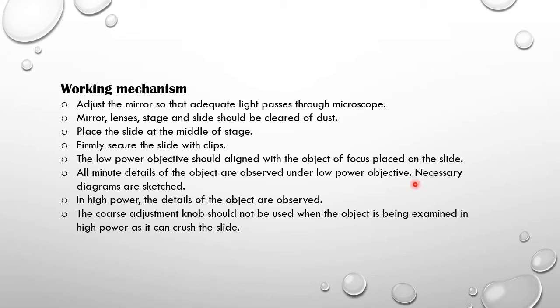Under low power objective, necessary diagrams are sketched. In high power, the details of the object are observed. The coarse adjustment knob should not be used when the object is being examined in high power, as it can crush the slide.